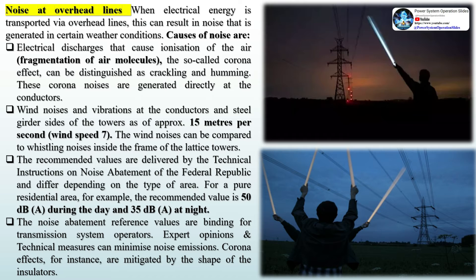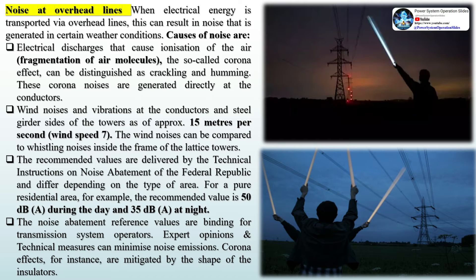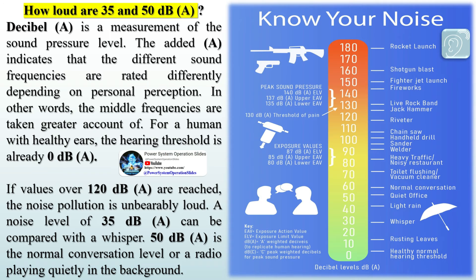Noise at overhead lines: when electrical energy is transported via overhead lines, this can result in noise generated in certain weather conditions. Causes of noise include electrical discharges that cause ionization of the air and fragmentation of the air molecules — the so-called corona effect — which can be distinguished as crackling and humming. These corona noises are generated directly at the conductors. Wind noises and vibrations at the conductors and steel girder sides of the towers occur at approximately 15 m/s wind speed. The recommended values are delivered by the technical instructions on noise abatement and differ depending on the type of area. For a pure residential area, the recommended value is 50 dBA during the day and 35 dBA at night.